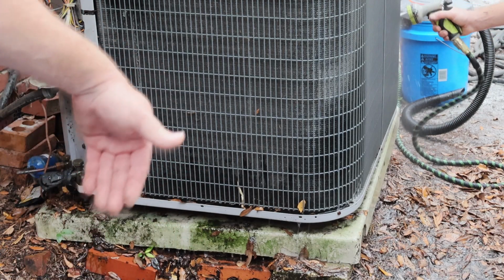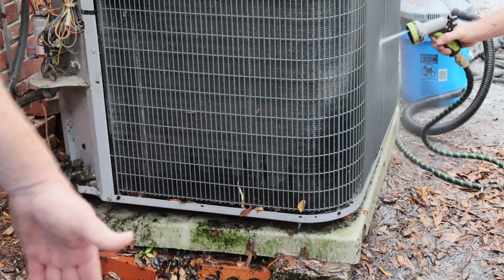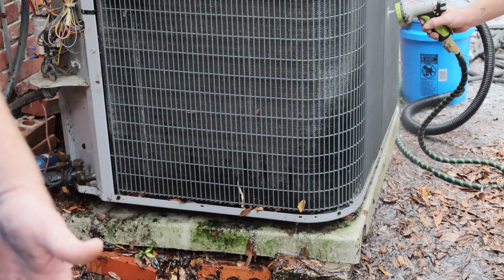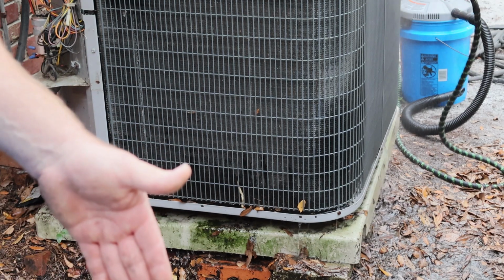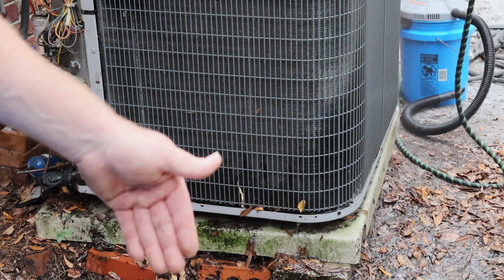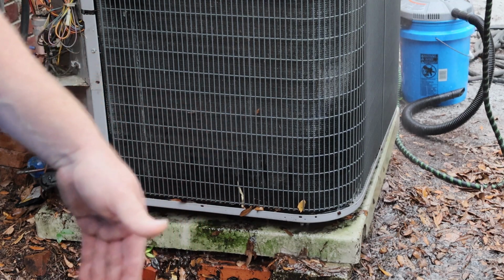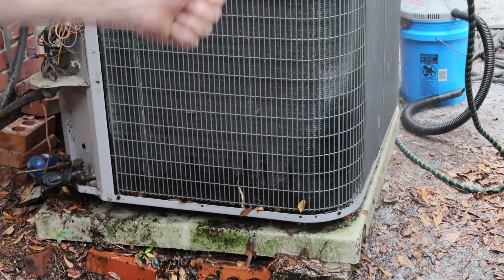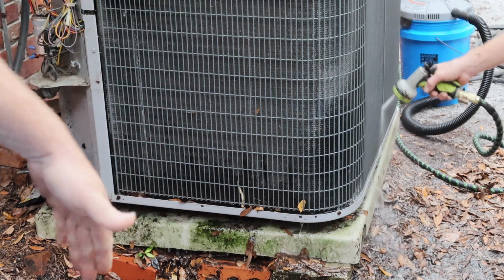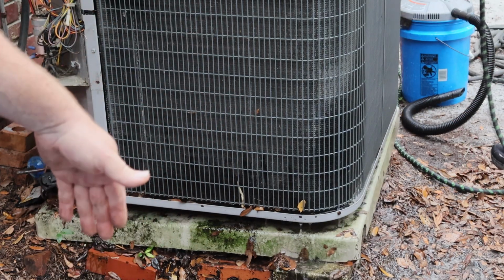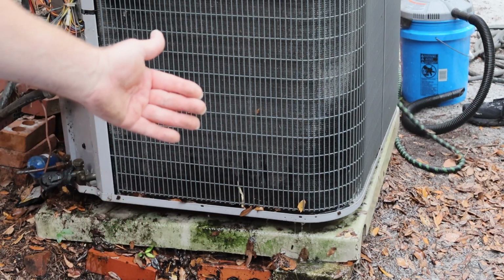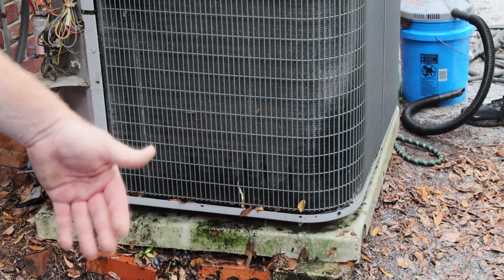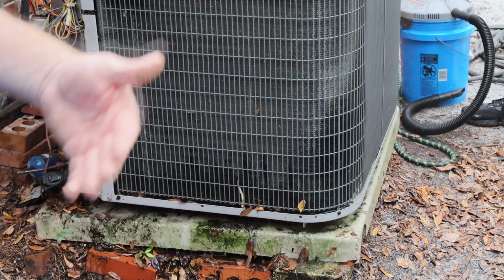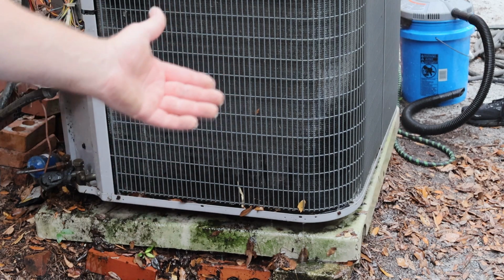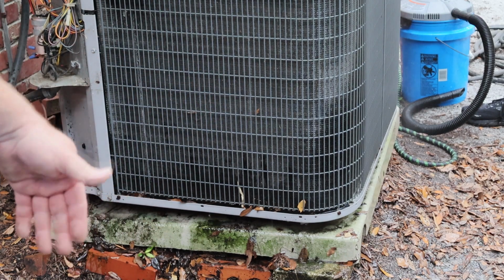It has to pull air through that coil. As it pulls the air through the coil, the refrigerant gives up the heat that's in it and discharges it out the top. So if you've got restriction and you can't move enough air, you're not going to have that transfer of heat that the machine needs to perform at its peak performance. So it's important to keep them clean.